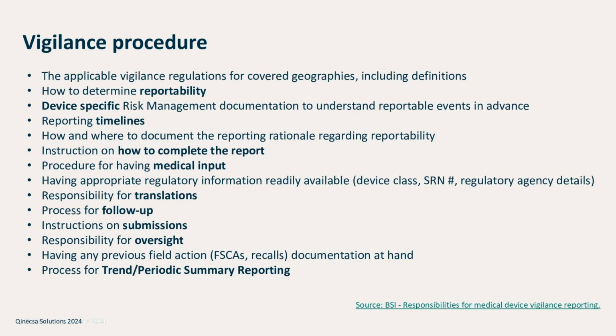There needs to be a procedure to determine reportability. So there needs to be a way to escalate a complaint to a reportable incident, and that needs to be done in compliance with whatever is already defined by the manufacturer in the post-market surveillance plan. The risk management file documentation is device specific. So it's not possible to have one template and use it for everything, because every device is different. Every device has specific risks. So it's essential that these risks are well understood by the pharmacovigilance departments, and when in doubt, have a procedure for contacting the QA department of the manufacturer for any clarifications.